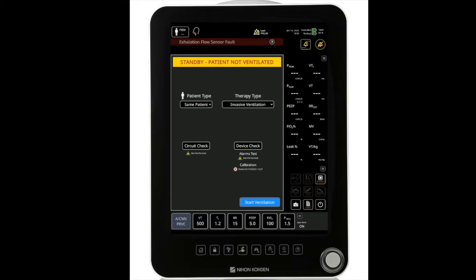I'm going to first show replacing the flow sensor and the flow sensor cable while the ventilator is in standby or not in patient use. Then also show how one can disable this sensor and replace a flow sensor during patient use without ventilation interruption.